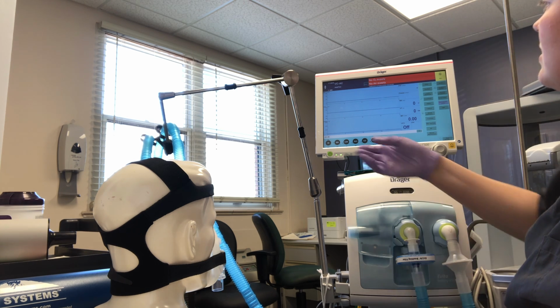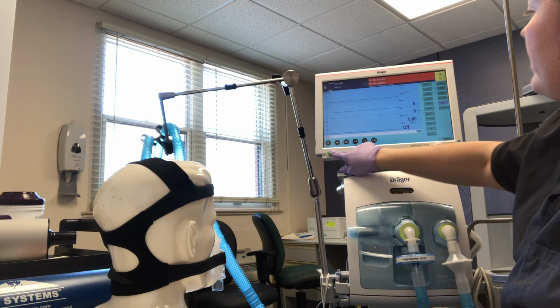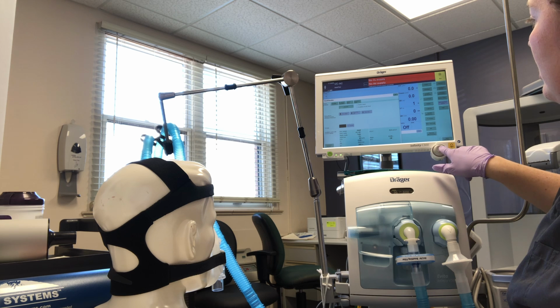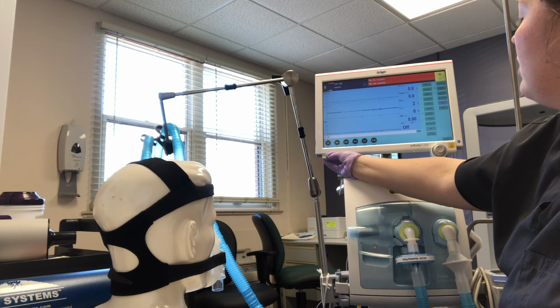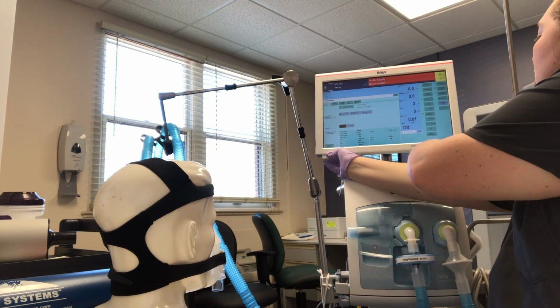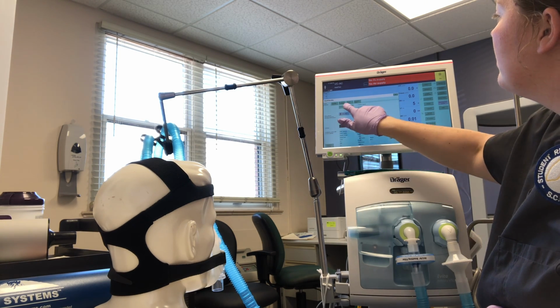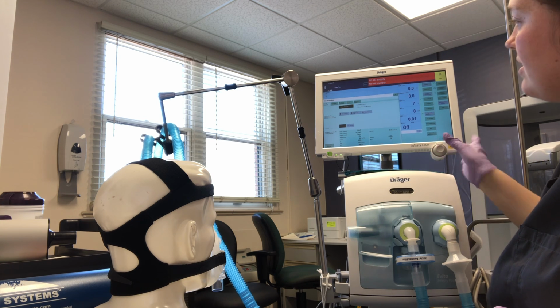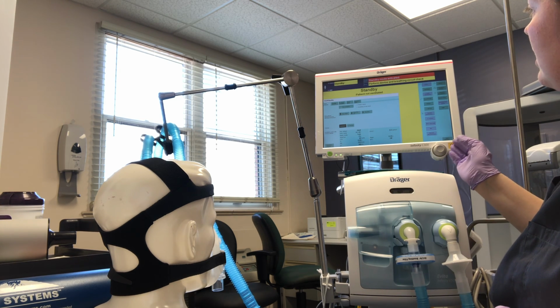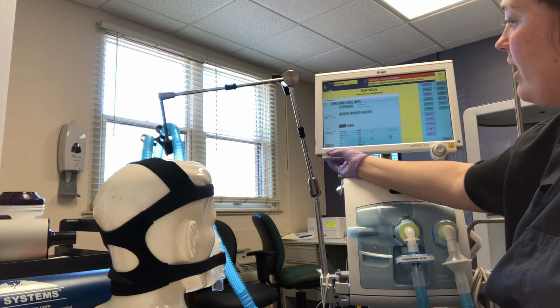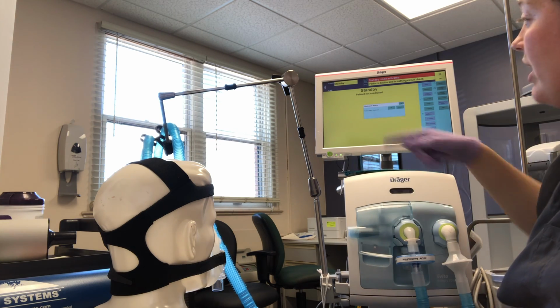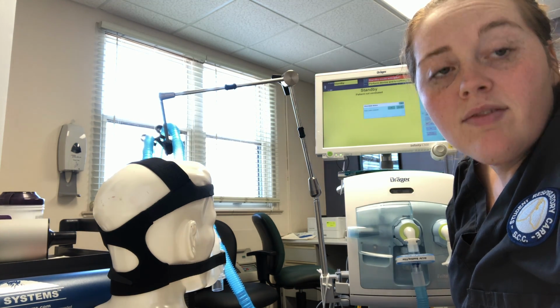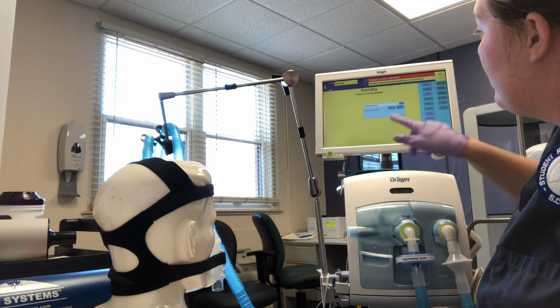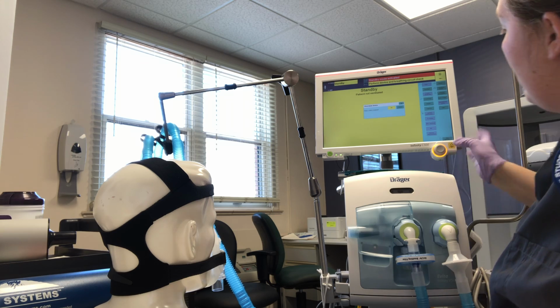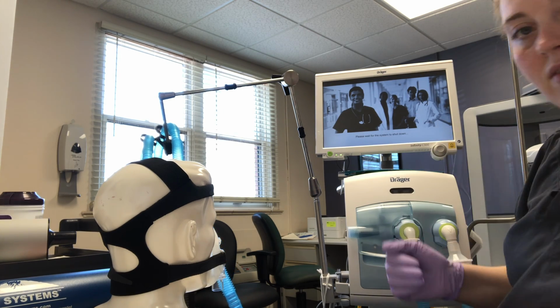Then to power off this device, I'll go back here. So you're going to push power. I'm going to go to standby. We're going to go back to standby. Okay, so we're in standby. Now we're going to shut off. Now it wants to make sure you shut off. It does that because they don't want you to accidentally shut off ventilation on your patient. So it asks you twice, and the answer is yes. We want to confirm shutdown. And then again, enter, and then it's going to let the system shut down.